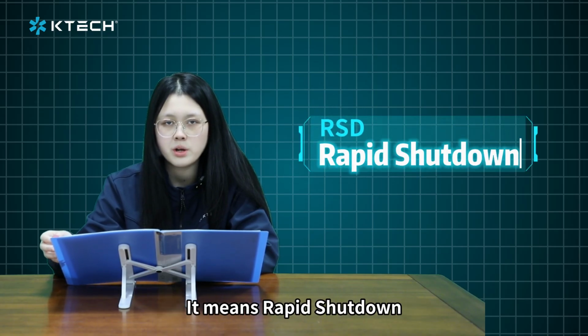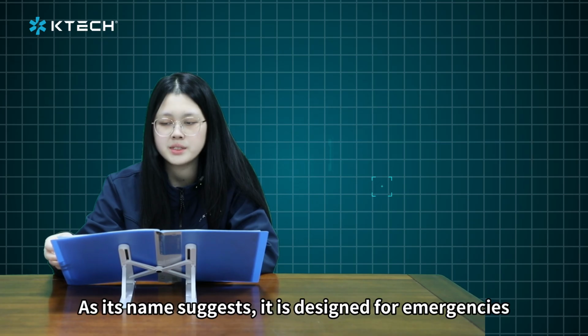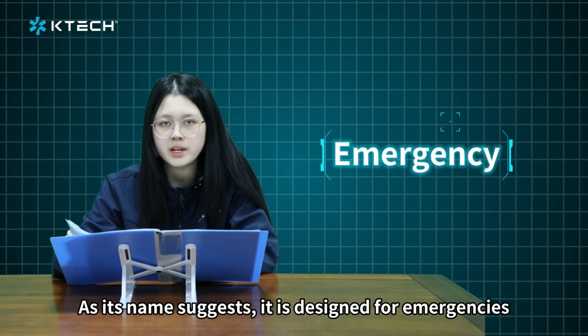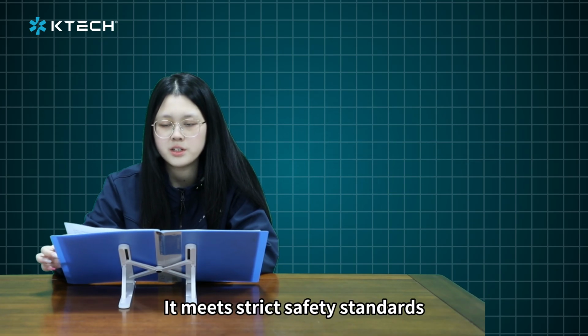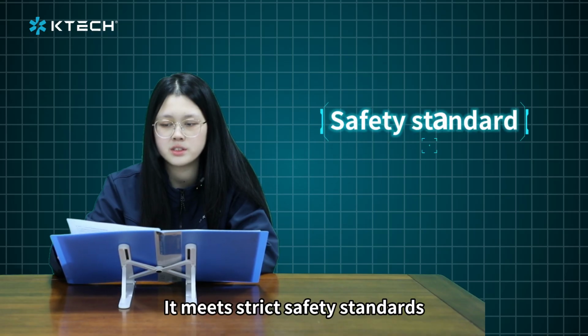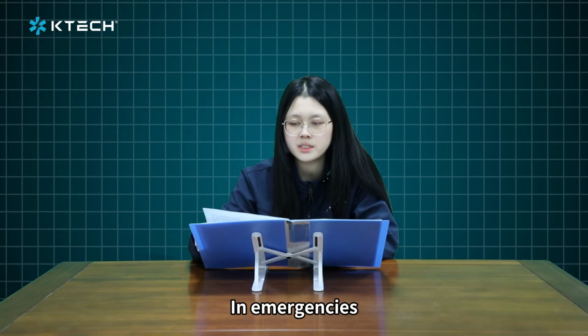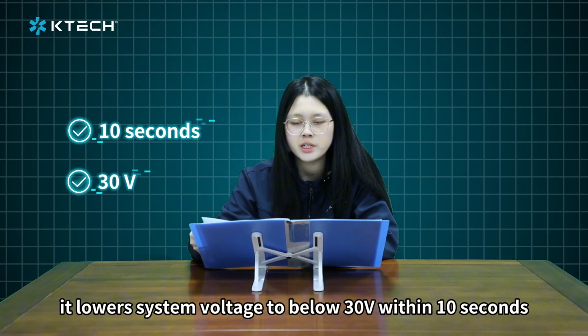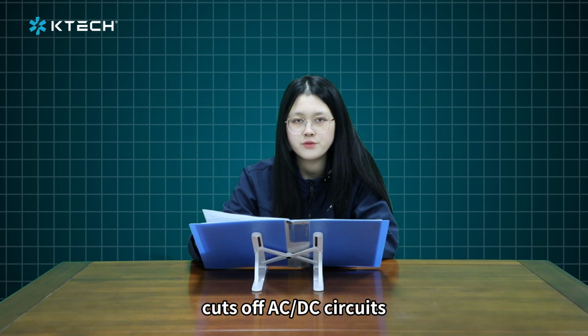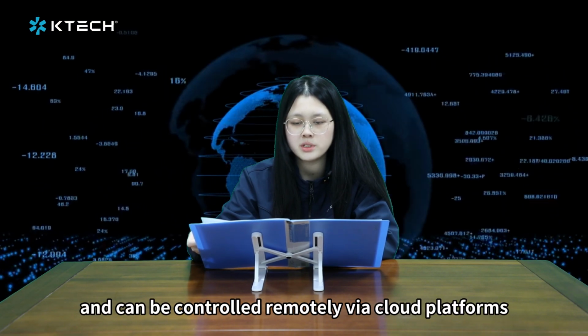Next is RSD, the emergency button. It means rapid shutdown. As its name suggests, it is designed for emergencies. It meets strict safety standards. In emergencies, it lowers system voltage to below 30 volts within 10 seconds, cuts off AC/DC circuits, and can be controlled remotely via cloud platforms.